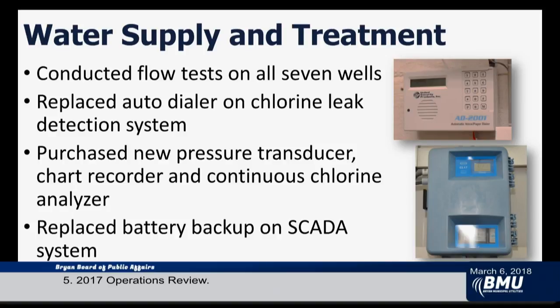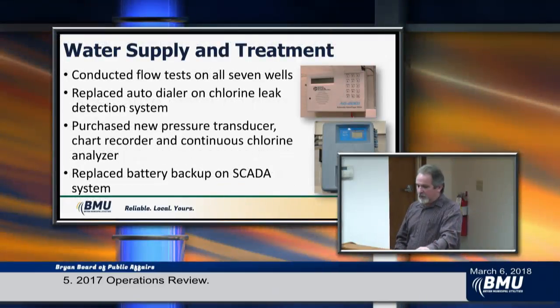At the water plant, we replaced some of the controls that had shown some age and some failure rates. The auto dialer on the chlorine leak detection system: if we do have a gaseous chlorine leak, the auto dialer dials the hazmat crew first and then alerts water personnel.